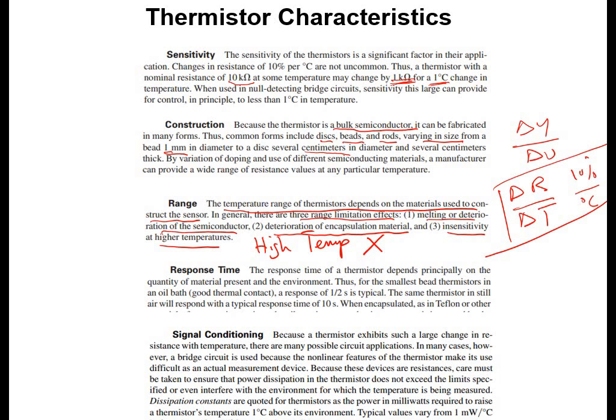The response time of the thermistor principally depends on the quantity of material present and the environment. For the smallest bead thermistor in an oil bath with good thermal contact, a response of 0.5 seconds is typical. The same thermistor in still air will respond with a typical response time of 10 seconds. So direct contact takes 0.5 s, while measuring temperature in air takes about 10 s.